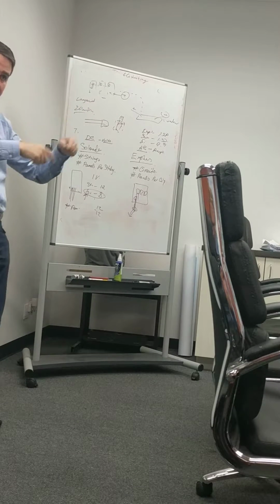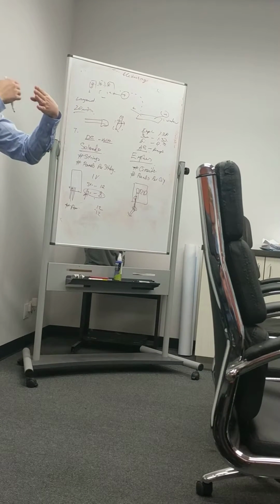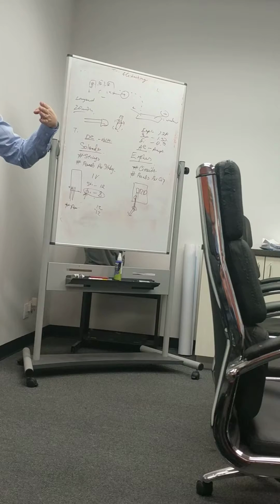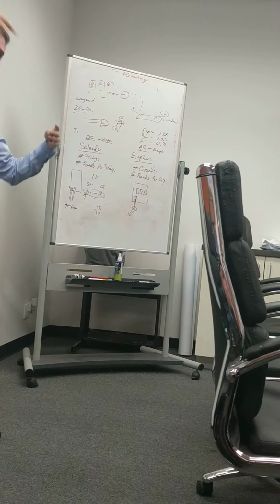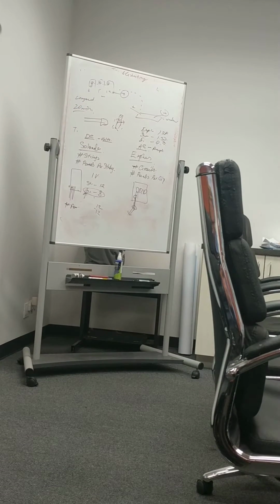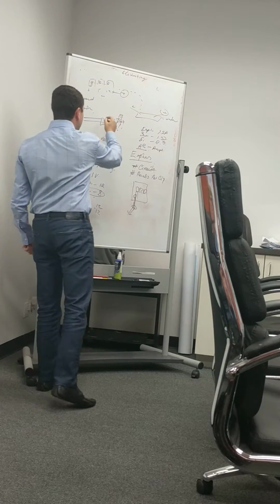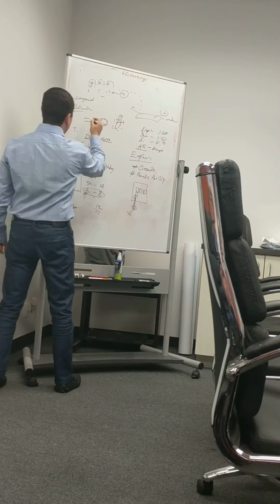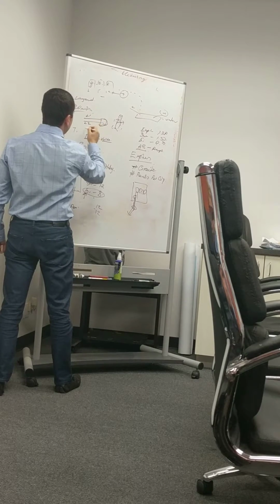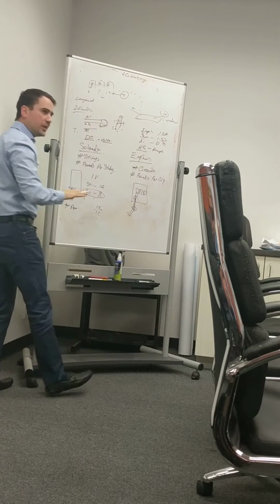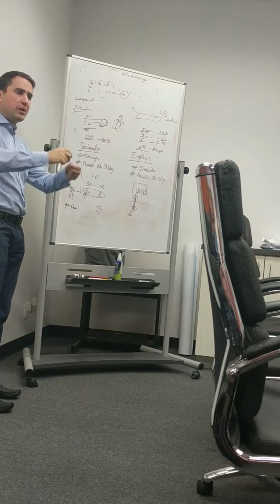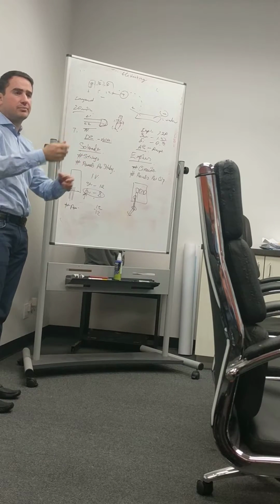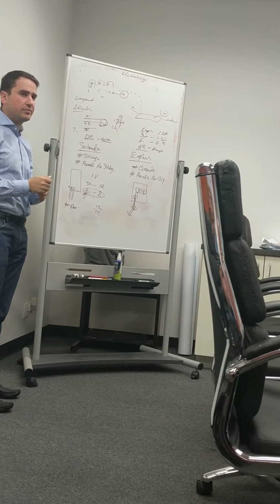You don't need to have a junction box to transition from the sunlight cable to regular cable. You just run the MC cable and that's it. With Enphase, you have to have a junction box at the end of each array. So you have line 1, line 2, and neutral. Most of them, they don't even have a neutral. So probably the wire nut is not done properly, that's it.